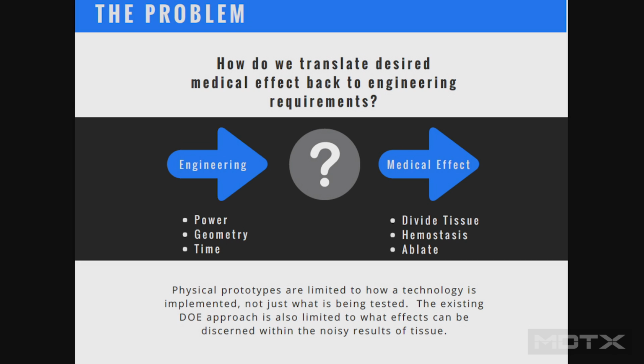So this boils down to primarily one concept, which is we all work on the engineering question sides of things, but the devices that we're making are all on the medical effect side of things. And what we want to do is add some insight to that black box that you get in the middle, which is, if I put in things like power, and I put in things like changing the geometry of the electrodes, or I change the balloon size, or I change the flow rate of the coolant, what effect does that have on the far side about my ability to ablate diseased tissue, or the ability to cut through things or stop bleeding? Those are the things on the far side that the medical community cares about.